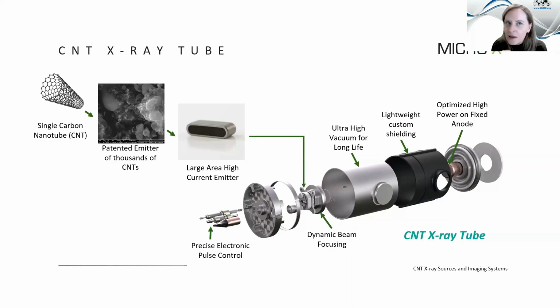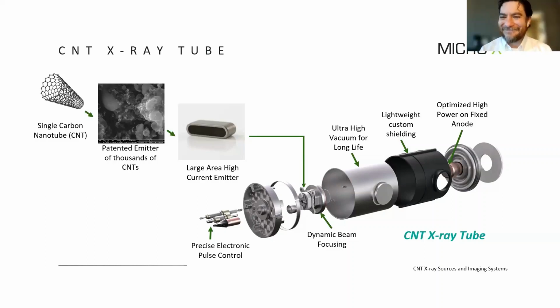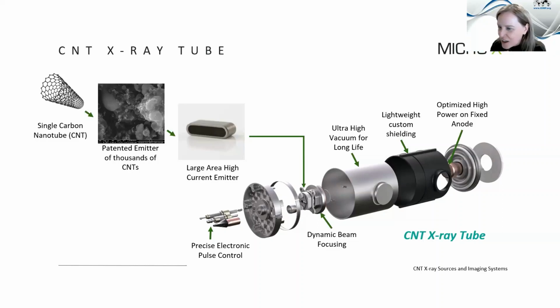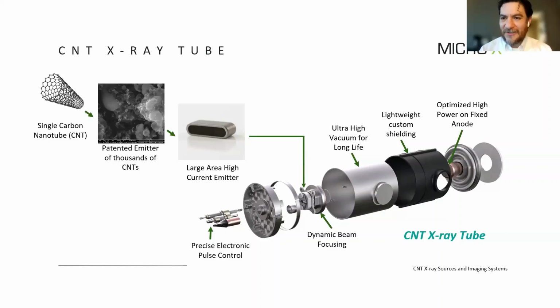If you are looking at imaging maybe larger bodies, would you need to produce carbon nanotube X-ray tubes with larger currents? I think we could. When people were looking at the currents that you presented, whether they are sufficient. So the medical tube that we have goes up to 100 milliamps right now at 120 kV, which is quite a decent amount of dose. And given the effectiveness of current digital detectors, for everything that a mobile X-ray imaging system does, we believe that that's sufficient.